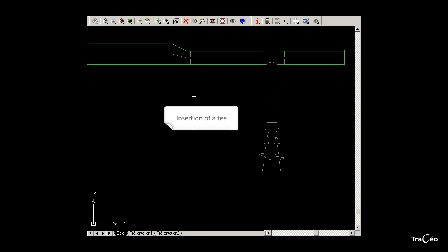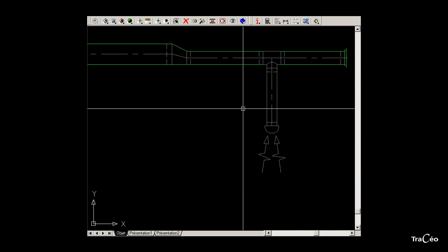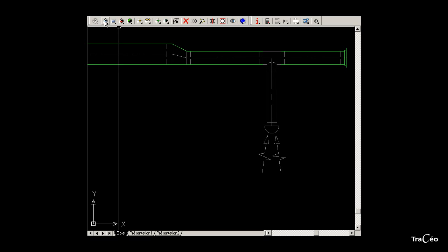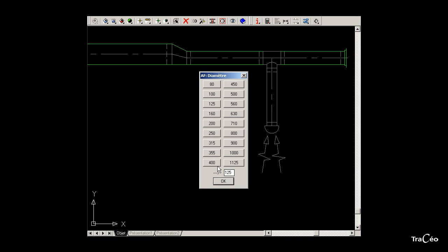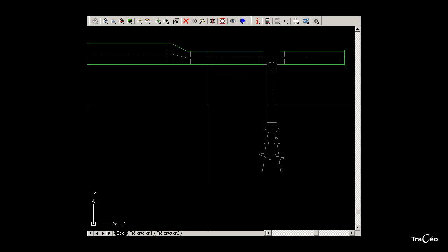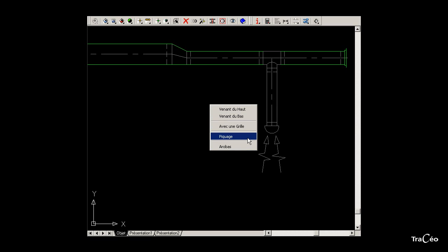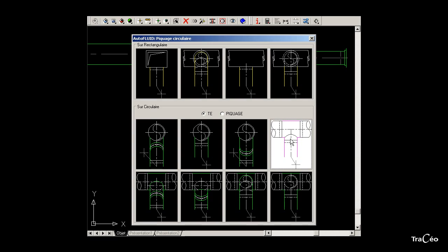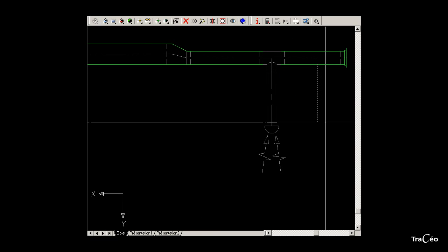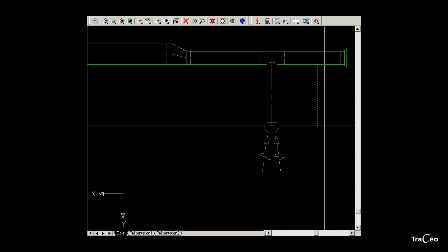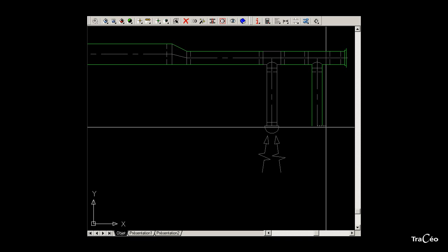To draw this circular branch, select the circular drawing command, then select the type of network and the profile size. Right-click to select the connection option. Instead of a tapping connection, select T and choose the appropriate T connection. Select the duct to connect to, then click to indicate the direction. The T appears.